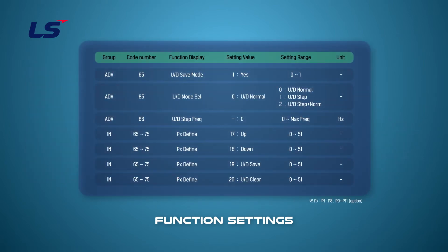Next, we will see how to save the operating frequency. By default, frequencies designated by Up or Down operation are not saved. However, if ADV 65 is set to Yes, the Up-Down function allows the operation frequency to be stored in memory when the Run command is turned off or tripped during constant speed operation, or when the power is cut off.